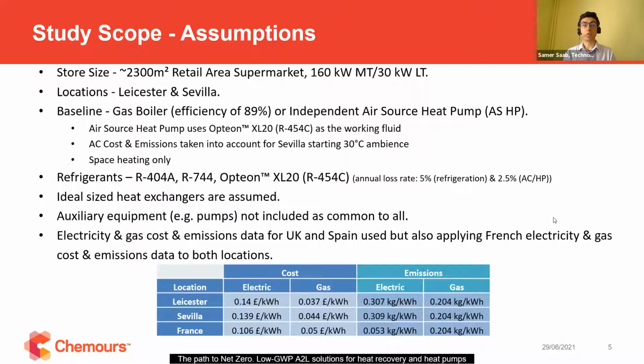In this study, we have also looked at three different refrigerant to replace 404A. Here we are only presenting the results for CO2 and 454C or Opteon XL20. And you can see on the screen the assumptions regarding the emissions or the leak rates that were considered in this study. An important assumption also would be that all heat exchangers were assumed to be sized ideally, which means we did not do any compromise on the sizing of these heat exchangers for economical reasons. All the auxiliary like the pumps were not included, as they are common to all technologies as well.